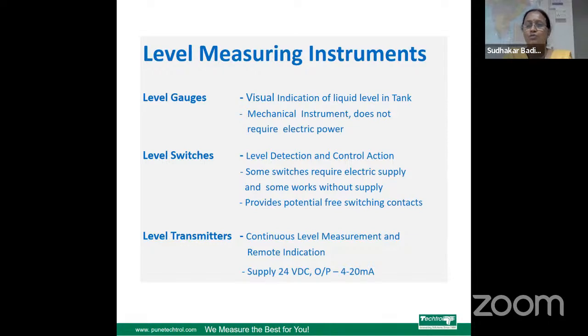Level gauges are used for visual indication of liquid level in the tank. They are mechanical instruments and do not require electric power. The level switches, they are used for level detection, and the output of these level switches is potential free switching contacts, that can be used for further control actions like pump on, pump off, or to generate alarms, or switch on the solenoid valves and off. So some of these level switches do not require electricity, like float type switches, and some switches require electric supply.